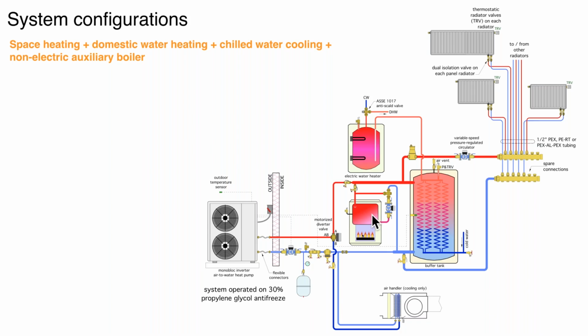If this is a conventional boiler, it's not designed to operate with sustained flue gas condensation. And we could potentially, especially in a retrofit situation, have a boiler that for years has operated well above dew point. So it has not experienced sustained flue gas condensation. And all of a sudden we've created a modified system that may force that boiler to operate at conditions that would cause sustained flue gas condensation. So you want some type of a protection valve, a mixing valve in there.